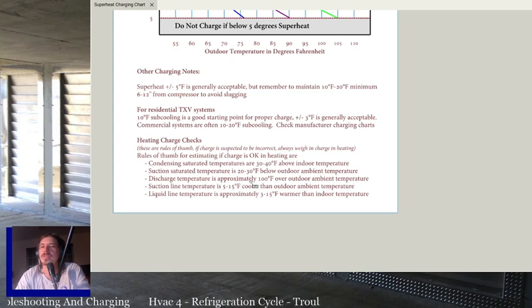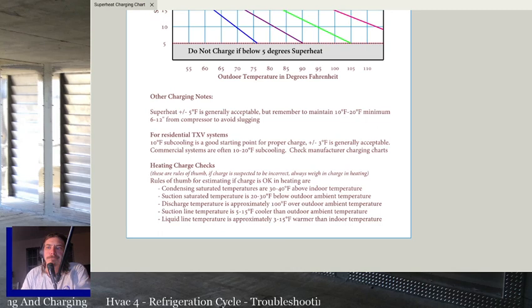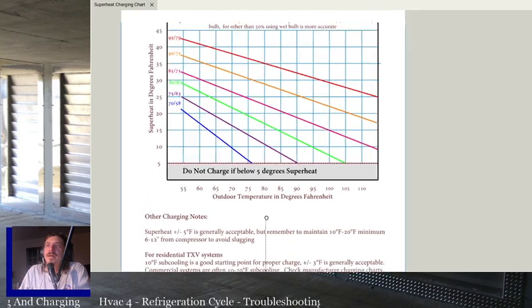Anytime your line temp is equal to the ambient that it's trying to give off or pick up heat from, odds are you've got a refrigerant issue there because it's superheating too much or it's subcooling too much. You're probably low on refrigerant there, because you should have basically a little bit of headroom. I don't know how else to put it, but you should have a little bit of space there. Unless you've got a gigantic, super efficient coil, there should be some differences between those line temps and the temps of the air that it's trying to either give off the heat to or pick up the heat from. Does that make sense? All right. So that's your best ways of check and charge.